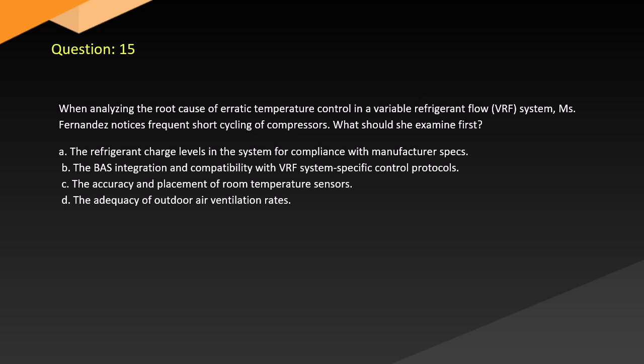Question 15. When analyzing the root cause of erratic temperature control in a variable refrigerant flow, VRF, system, Fernandez notices frequent short cycling of compressors. What should she examine first? A. The refrigerant charge levels in the system for compliance with manufacturer specs. B. The BAS integration and compatibility with VRF system-specific control protocols. C. The accuracy and placement of room temperature sensors. D. The adequacy of outdoor air ventilation rates.